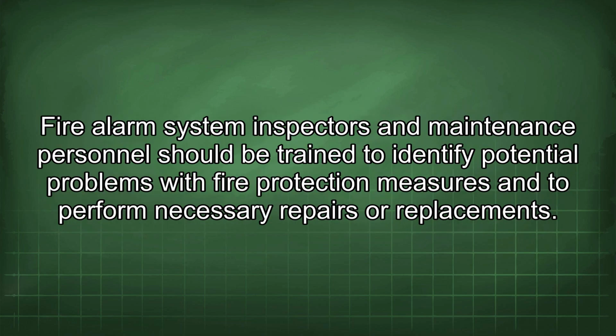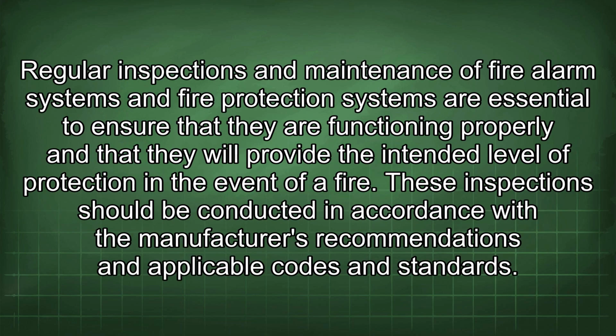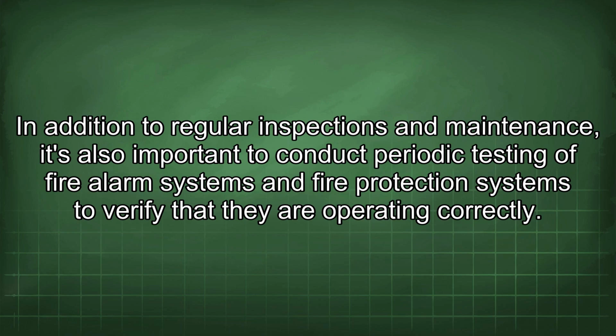Fire alarm system inspectors and maintenance personnel should be trained to identify potential problems with fire protection measures and to perform necessary repairs or replacements. Regular inspections and maintenance of fire alarm systems and fire protection systems are essential to ensure that they are functioning properly and that they will provide the intended level of protection in the event of a fire. These inspections should be conducted in accordance with the manufacturer's recommendations and applicable codes and standards. In addition to regular inspections and maintenance, it's also important to conduct periodic testing of fire alarm systems and fire protection systems to verify that they are operating correctly.